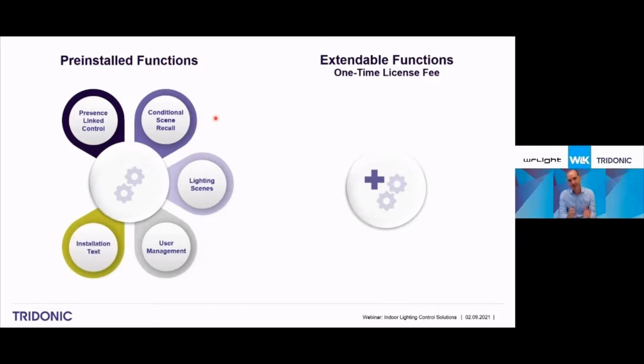To make work on site hopefully easy, we have features like an installation test. You connect all luminaires and sensors to the DALI line, power on the entire circuit, and sceneCOM Evo can run a quick test to check if the wiring was done correctly and if all luminaires are connected according to plan. These are cool features for installers and commissioners, hopefully helping them not waste time on site during installation.